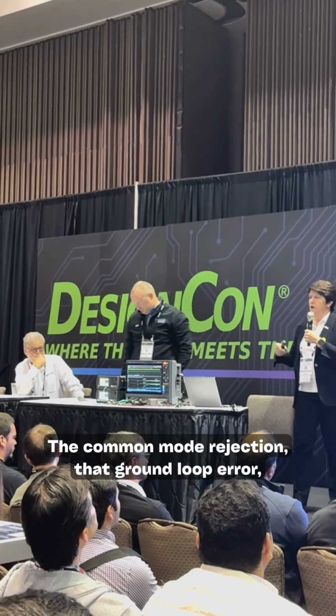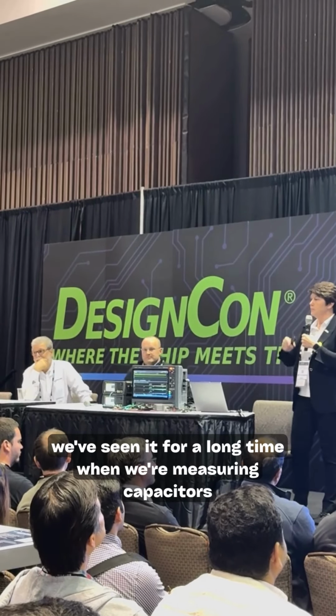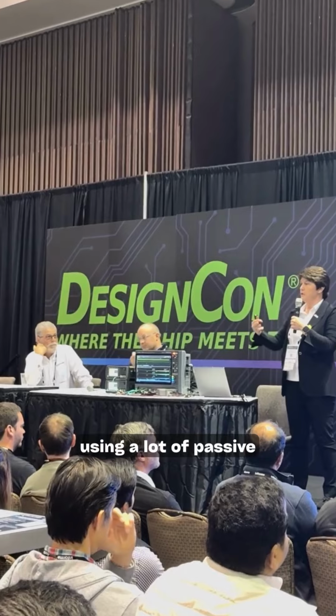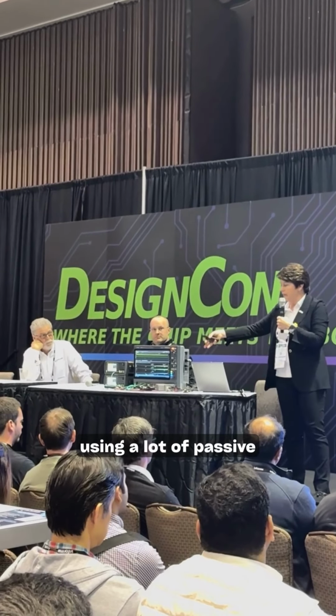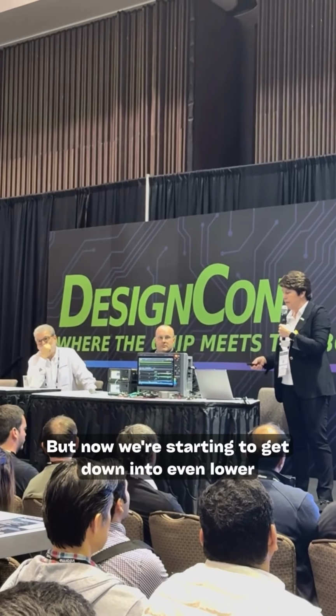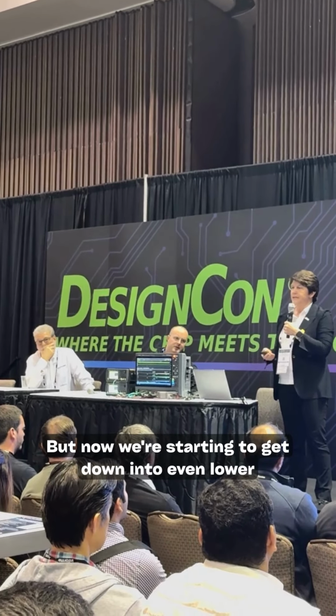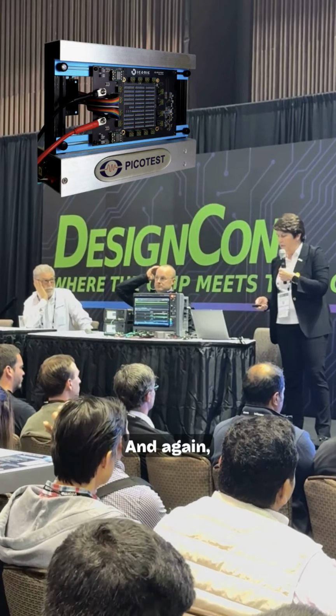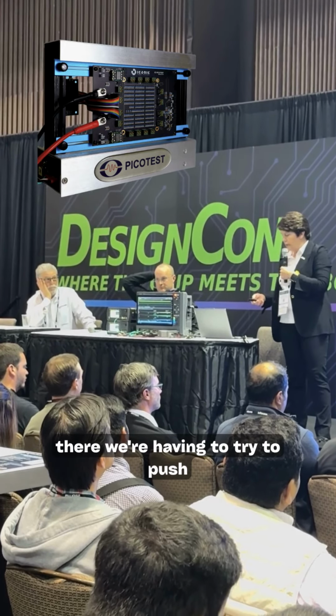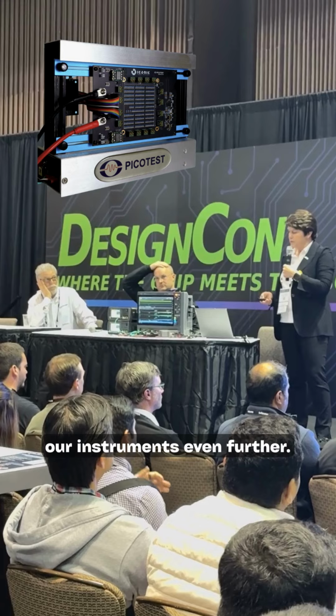Common mode rejection, that ground loop error, we've seen it for a long time when we're measuring capacitors, and we've been using a lot of passive transformers and the solid state ones. But now we're starting to get down into even lower impedances. With a 2,000 amp power rail, we need to measure micro-ohms. And again, there we're having to try to push our instruments even further.